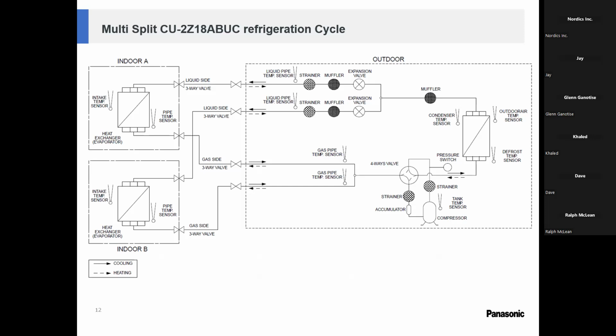So that is why we always insist, please do not use filter dryers. The reason we don't want filter dryers is because we have enough strainers in the system, and using a filter dryer will just cause more resistance for your gas, for your refrigerant flow. So please keep that in mind as well.